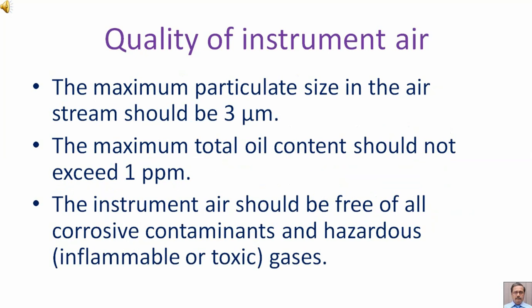The maximum particulate size in the air stream should be 3 micrometer. The maximum total oil content should not exceed 1 part per million. The instrument air should be free of all corrosive contaminants and hazardous, that is, inflammable or toxic gases.